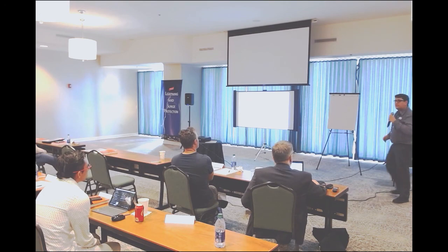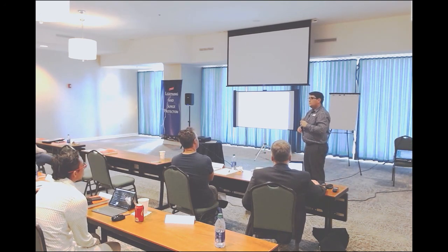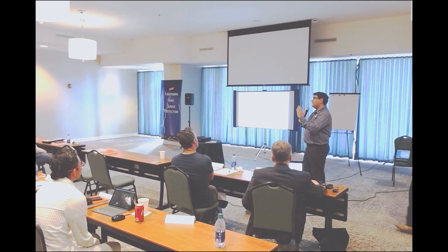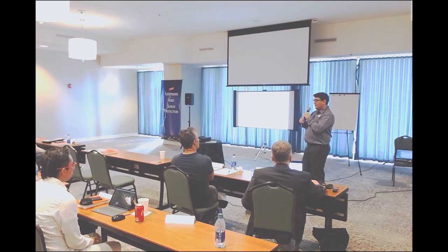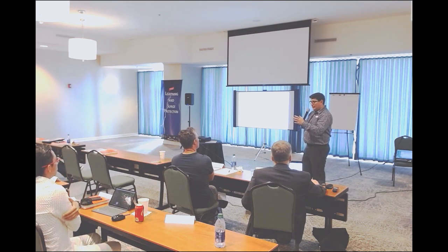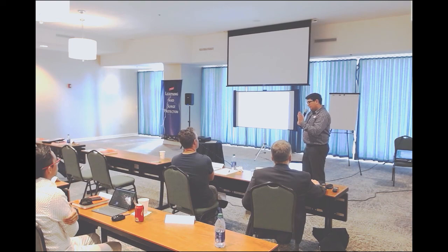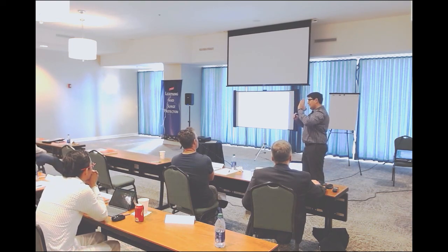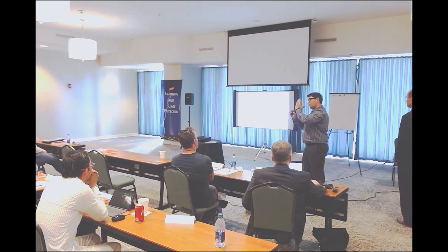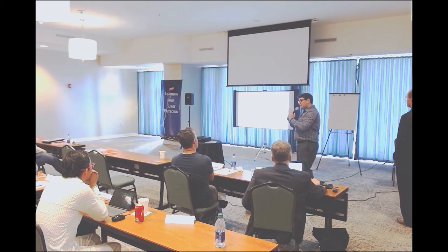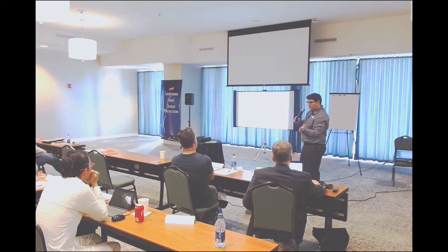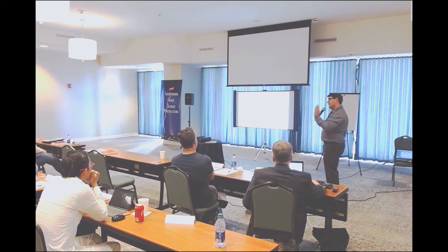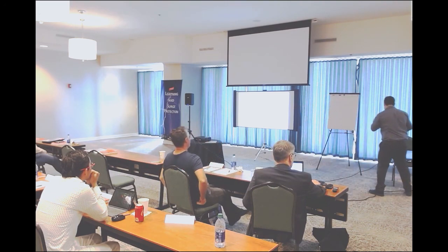What do you mean 45? Look, even if I went taller, I still could not. I had to go 2 or 3, maybe 4 feet taller just to have that rolling sphere cover the front. And obviously, the taller the rod became, wind loading and everything became a problem. Because of the height of the building, going higher, you can imagine if it's a sphere, would not necessarily move the sphere to the right. You'll have to significantly increase height to get that horizontal distance. So that's the reason why going for a smaller rod with a 45 degree actually moved it the amount of distance horizontally that I needed.